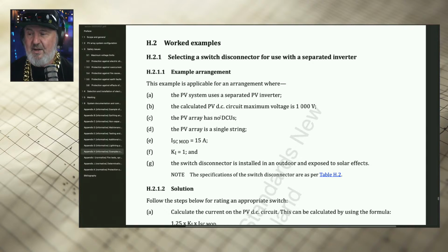There are no DCUs. Now, why does this matter, DCUs or DC conditioning units? I actually covered this in a previous Toolbox Tech Talk last week somewhat. DCUs or DC conditioning units, often referred to as optimizers by the marketing people, are a device that sits between a panel and the string to which the panels connect. And it means that the output voltage and current is controlled by the DCU, not by the panel. And so there are more different calculations. So effectively, the DCU determines the maximum current from the module, not the module itself. So to keep it simple, we're saying there's no DCUs.